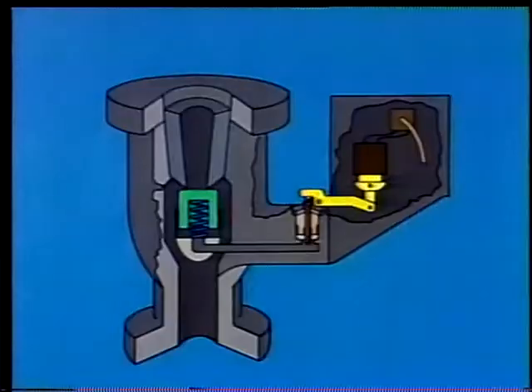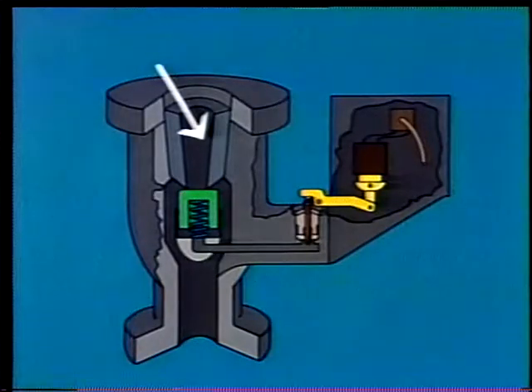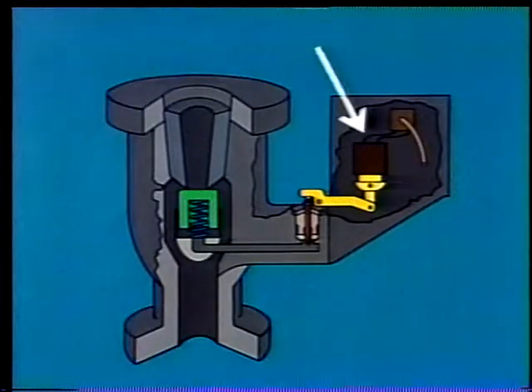Okay, now let's go on to the second pressure relief device we're going to look at in this segment, the pilot actuated or PA relief valve. This type of pressure relief device is known by any of several names: power-actuated pressure relief valve, electromatic relief valve, pressure-matic relief valve, but they all mean about the same thing. Regardless of what you call it, a PA relief valve consists of two major components: the valve itself, which is similar in shape to other valves we've seen, and a separate pilot device that senses changes in system pressure and tells the valve when to open.